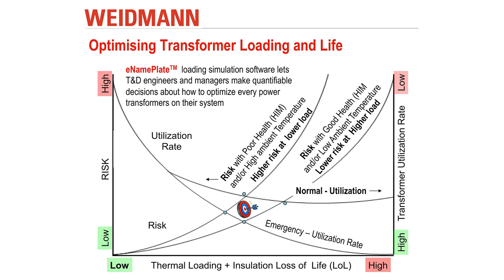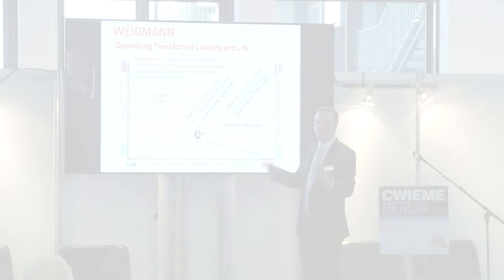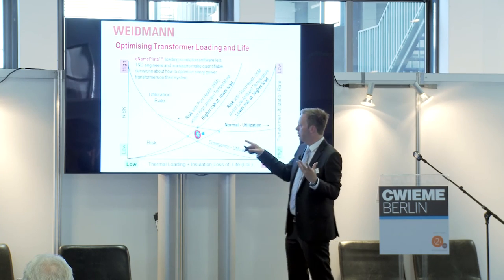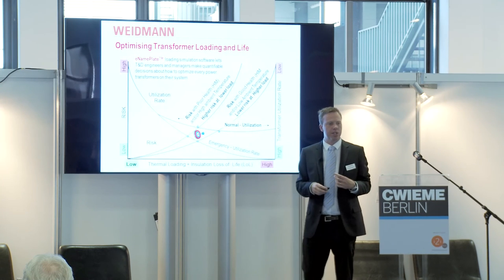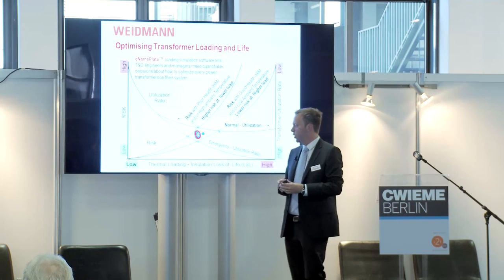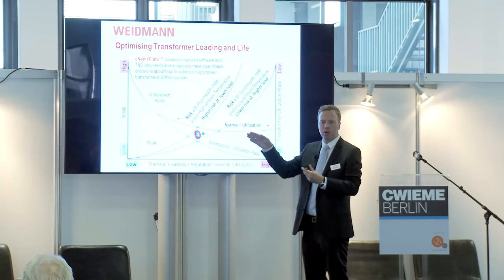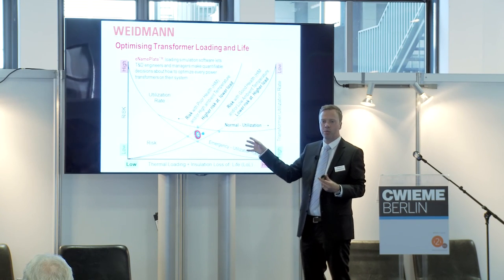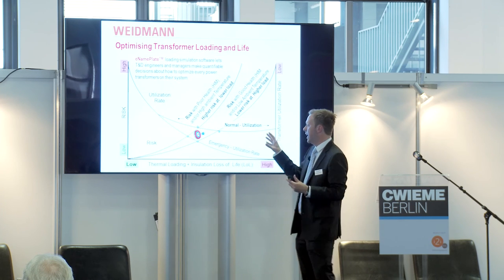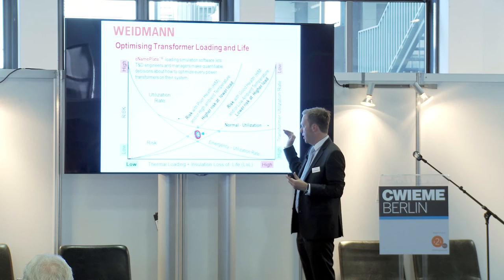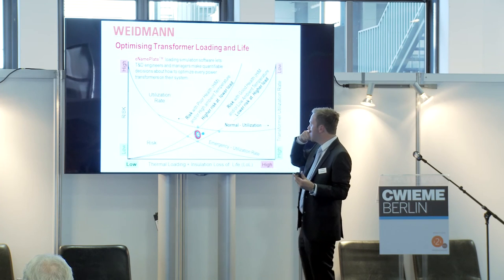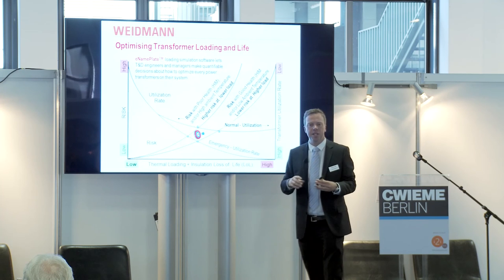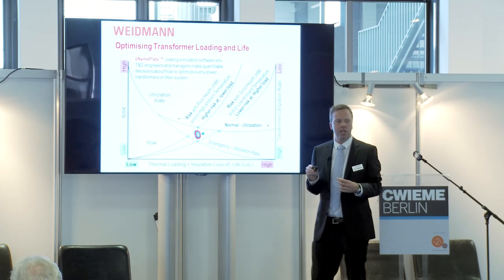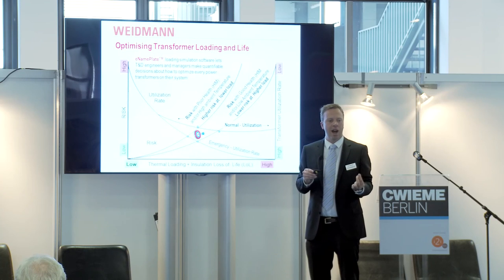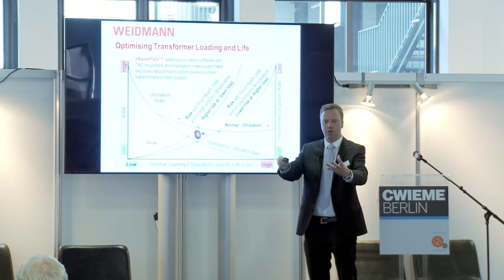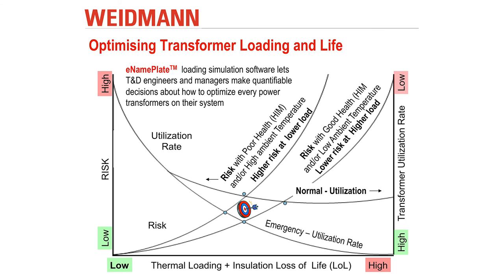So finally, what are we actually looking for? We're looking for the sweet spot, really, as an end user, as an asset owner. The sweet spot is how do I manage my risk and my loss of life on a transformer without having a failure. So I have to look at my emergency contingency plans, my utilization rate, my risk, my health index. From there, I'm trying to work out the most efficient way I can run this asset, this transformer. That's ultimately what we're trying to achieve here.